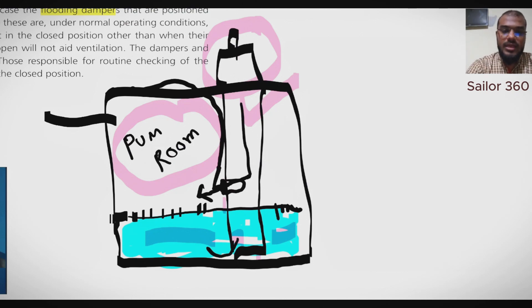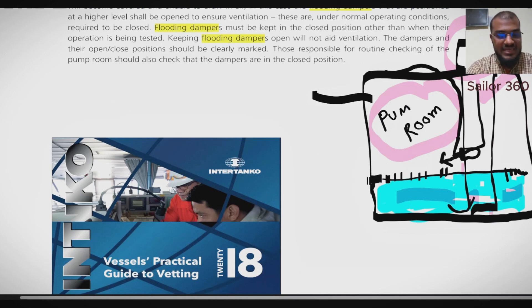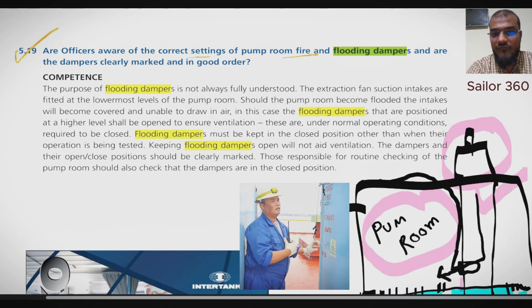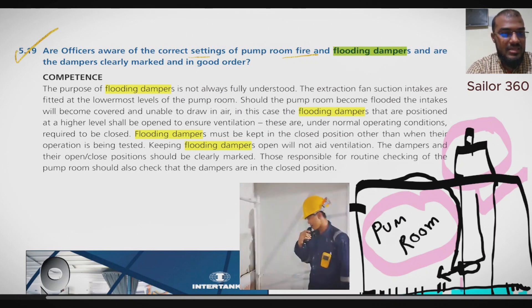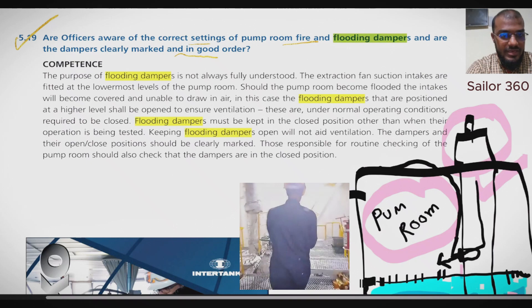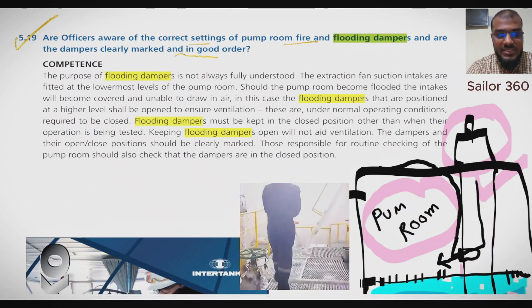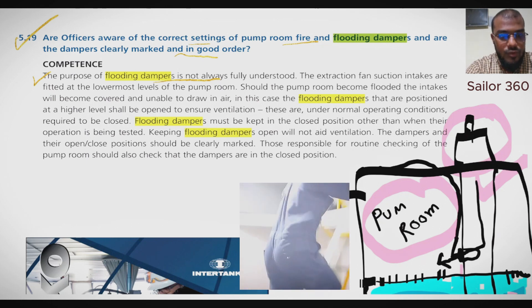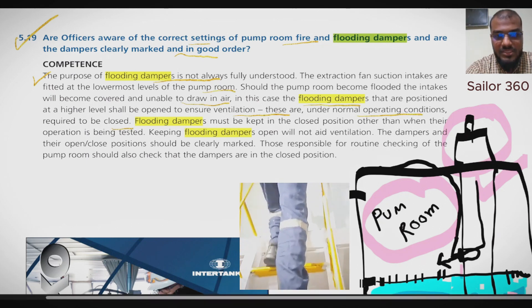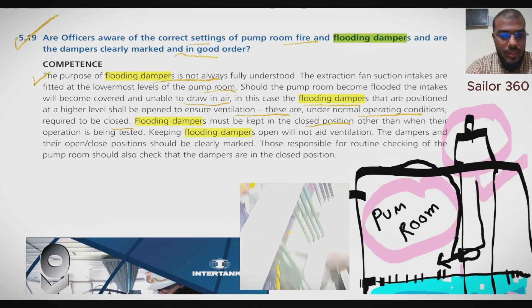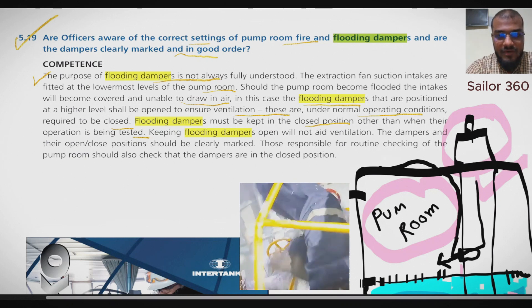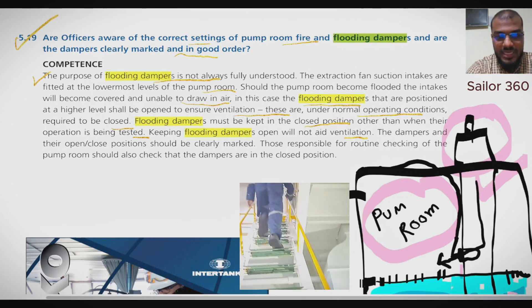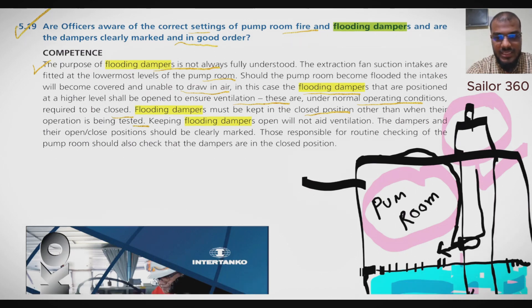Now I am going to read from the INTERTANKO guidelines regarding the flooding damper. It says: are officers aware of the correct setting of pump room fire and flooding dampers, and are the dampers clearly marked and in good order? The purpose of flooding dampers is not always fully understood. The extraction fan suction intakes are fitted at the lowermost levels of the pump room. Flooding dampers must be kept in the closed position other than when their operation is being tested — keeping flooding dampers open will not aid ventilation. The dampers and their open and closed positions should be clearly marked.